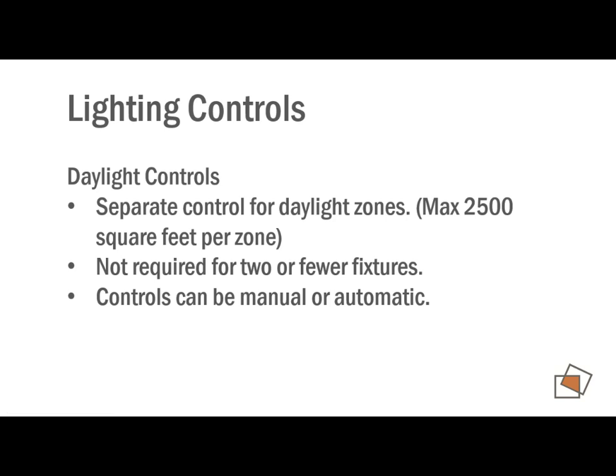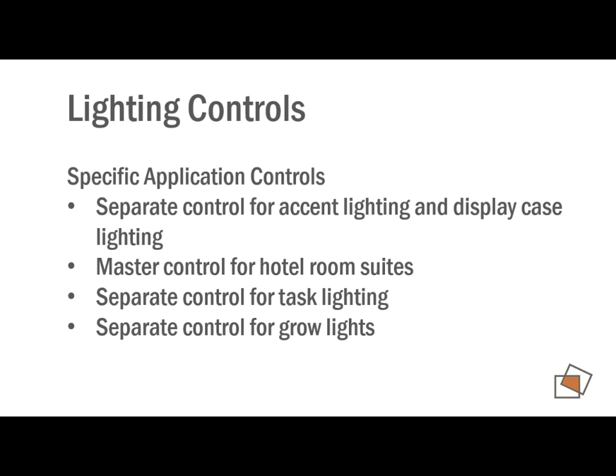The code's just trying to make it to where the users are able to turn off lights that just aren't necessary. It's that demand control piece that we talked about. So then it makes some provisions for specific applications. If you've got accent and display case lighting, you have to have separate control for that. You can't just control it with the overall room. You need to have a master control for hotel room suites. Task lighting needs to have its own control, and then it has a line in there for any grow lights to be on their own control too. So I guess the code's expecting a big boon in grow light usage.